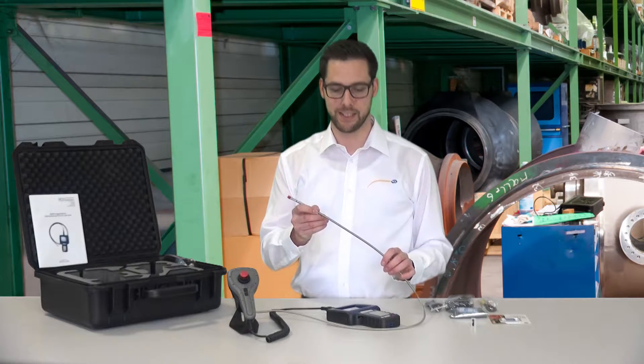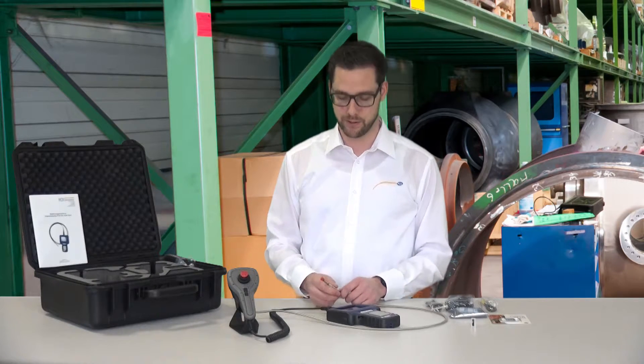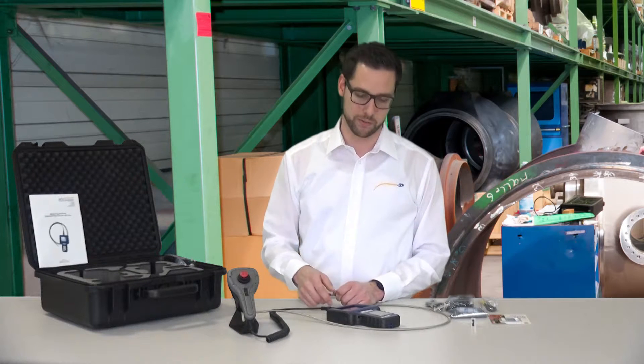I would now like to go into details about the technical specifications of the PCVE370HR endoscope. The flexible cable is 1m long and has a wire mesh braid. The picture sensor has a resolution of 640x480 pixels. Videos are recorded at a picture rate of 30Hz. The lighting happens automatically and you can dim it using the handset. The depth of field is 1.5 to 10cm. That is the focus area with which the endoscope can automatically record.